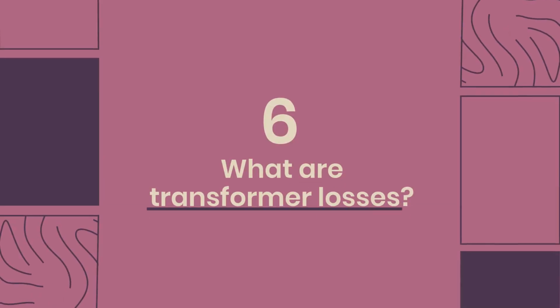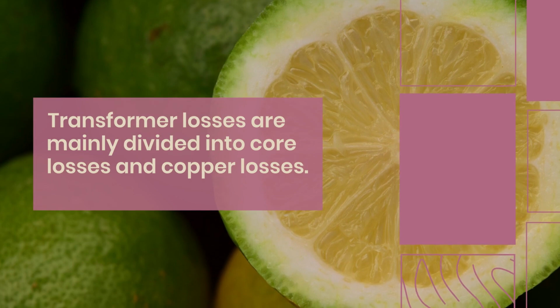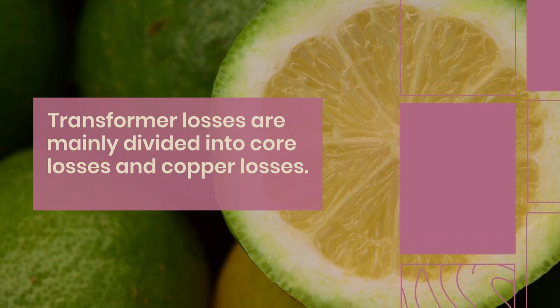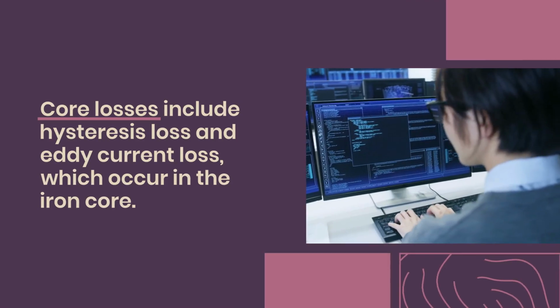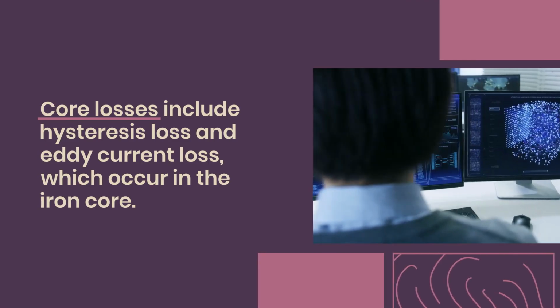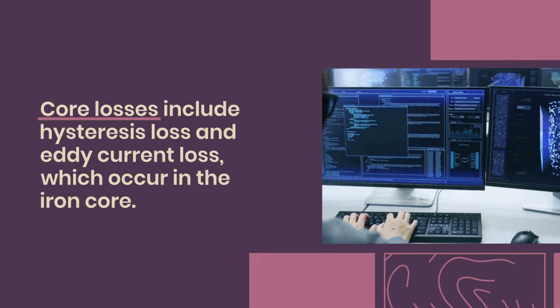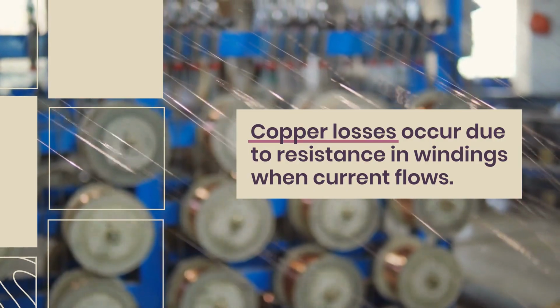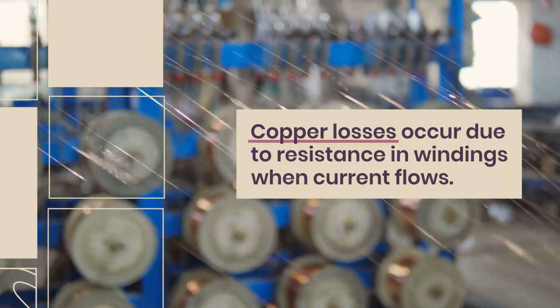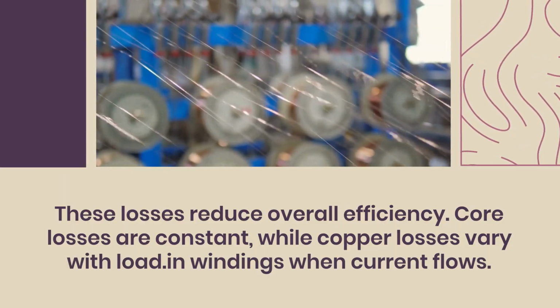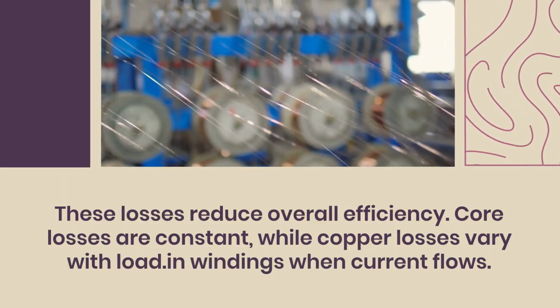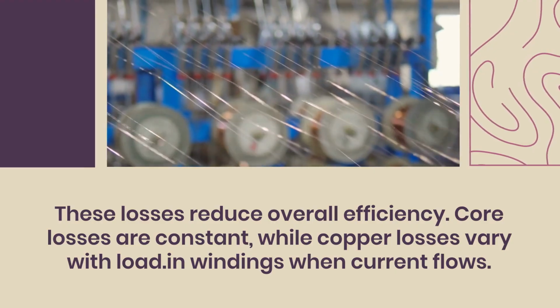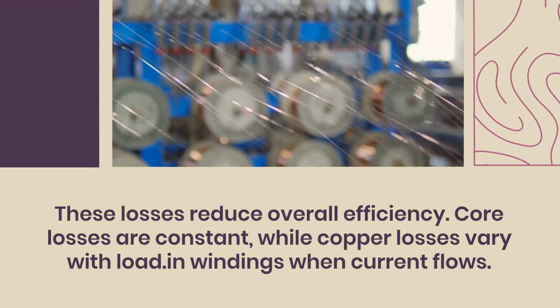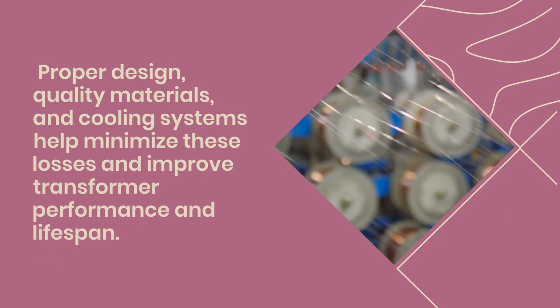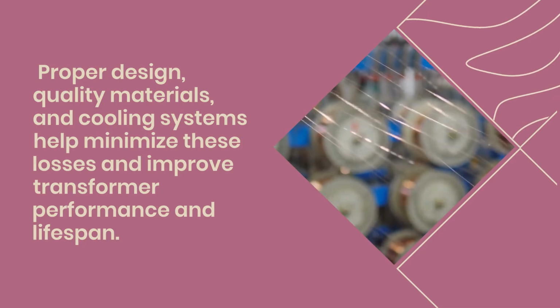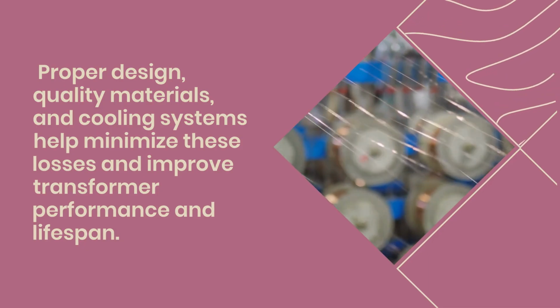6. What are transformer losses? Transformer losses are mainly divided into core losses and copper losses. Core losses include hysteresis loss and eddy current loss, which occur in the iron core. Copper losses occur due to resistance in windings when current flows. These losses reduce overall efficiency. Core losses are constant, while copper losses vary with load. Proper design, quality materials, and cooling systems help minimize these losses and improve transformer performance and lifespan.